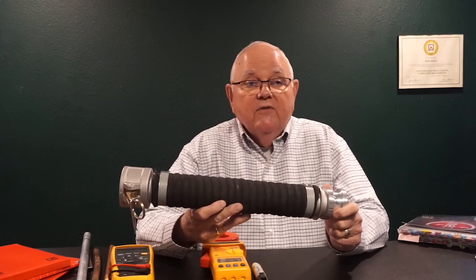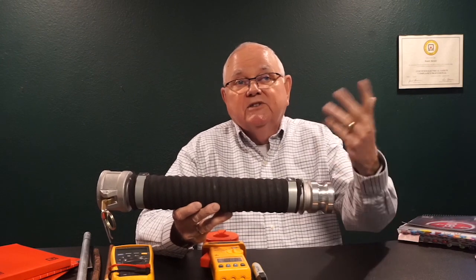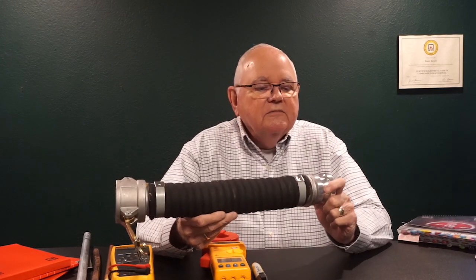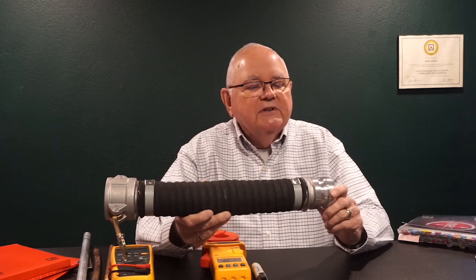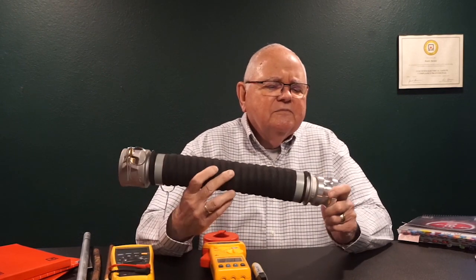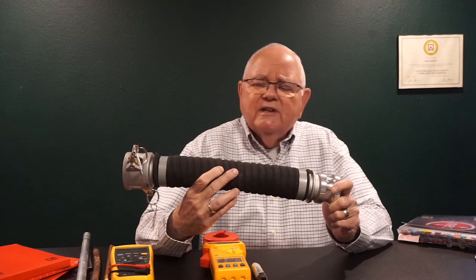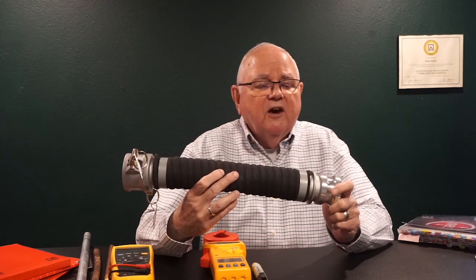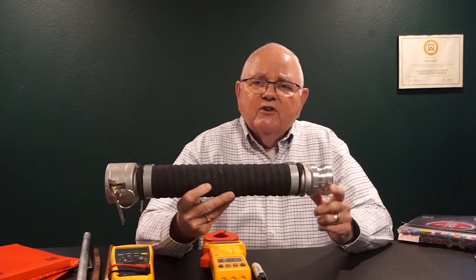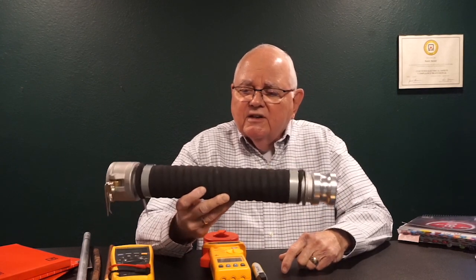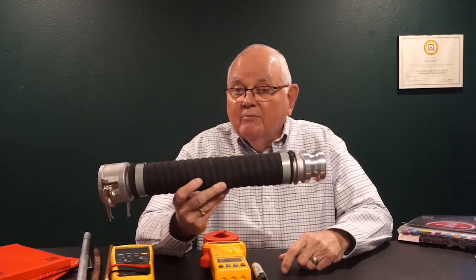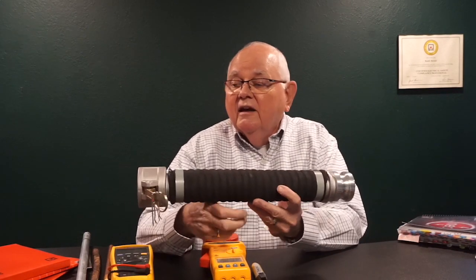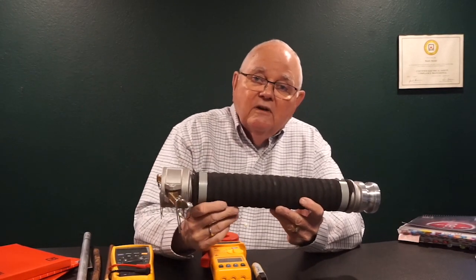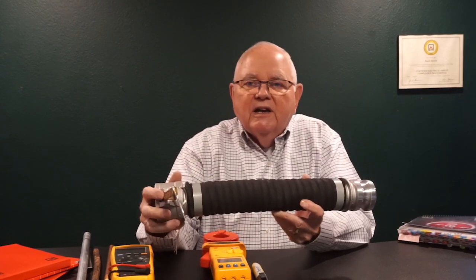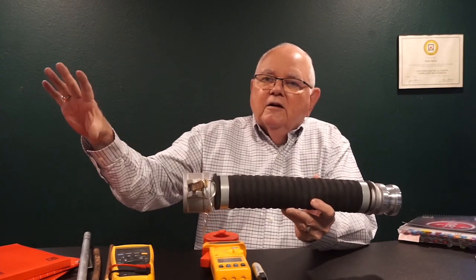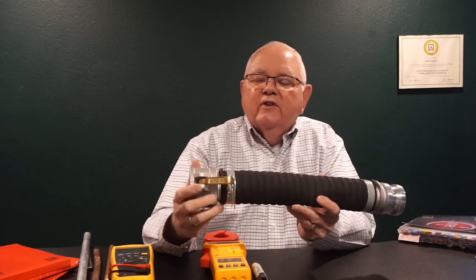Or I could get some flammable vapors off that liquid. Once I've opened it up and I start pumping, I could get some vapors out of it. That's an EPA consideration as well, but that's separate. So I better make sure that I don't get any sparks. And sure enough, I can off of something like this, because I'm going to create some static electricity, right? As this flammable liquid flows through this rubber hose, I'm probably going to strip some electrons out of that tank, and they're going to accumulate in my truck over here. So that's going to leave a positive charge on my tank, and the excess electrons will be a negative charge over here in my truck.